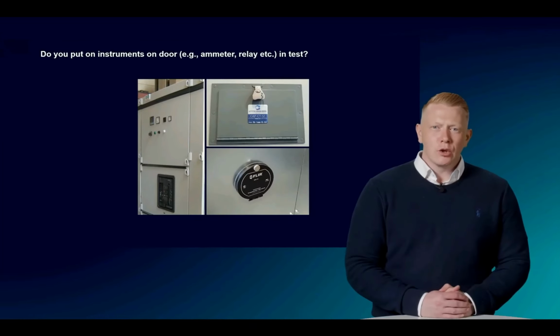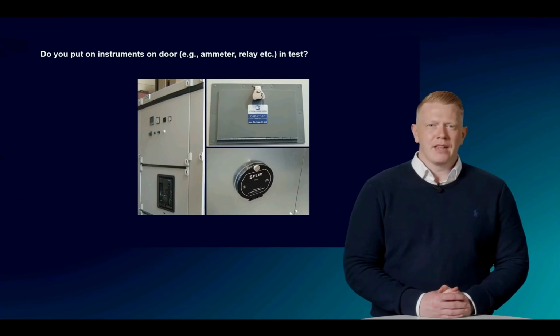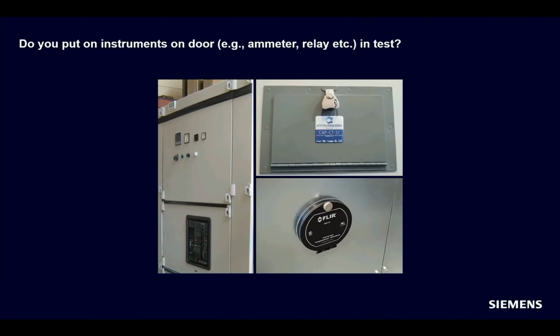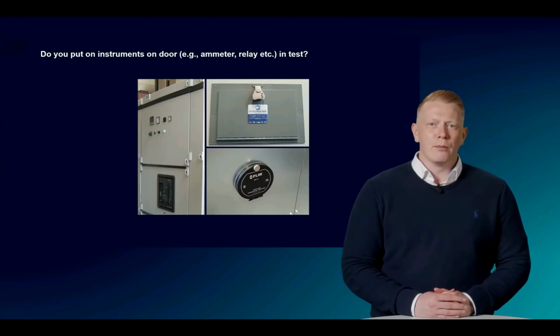Do you put on instruments on doors, for example, ammeters, relays or something, in tests? This is a very important topic. Usually, switchboards are equipped with multiple devices or instruments on the doors. And it should also be ensured that these devices do not fly away from the board as defined in Criterion 2 of the IEC Technical Report 61641. Our tests have also included typical door-mounted devices such as ammeters, IR monitoring windows, relays and such. These tests have been passed.